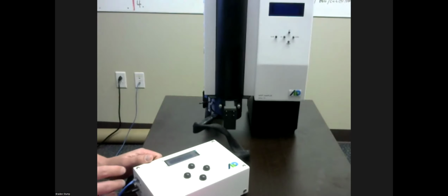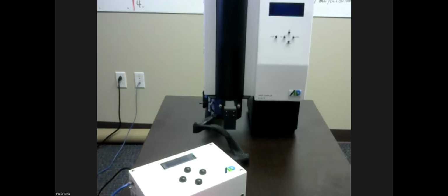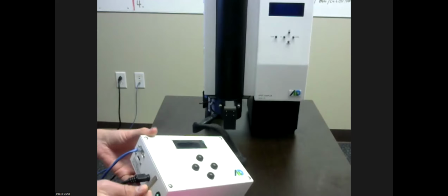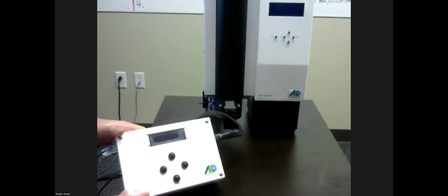In my case, I was wanting to show you guys some files on the instrument while it was operating. However, we do have a new way to pull log files off of the instrument, specifically the TLC. It should allow you to quicker access information. So I have a little Handix branded USB flash drive here.